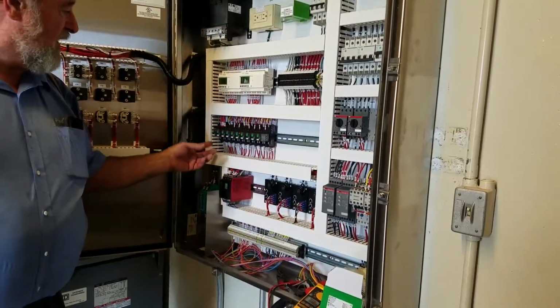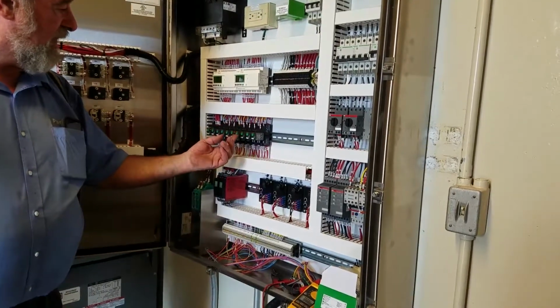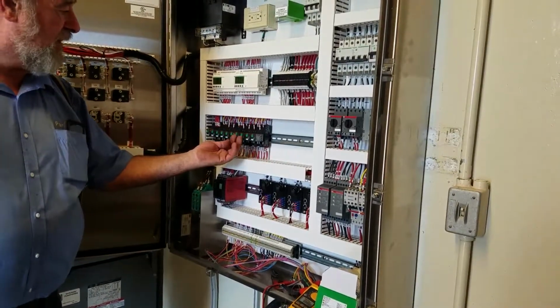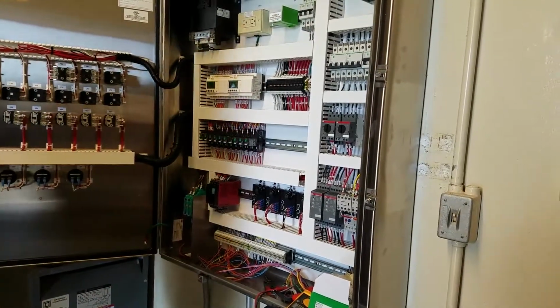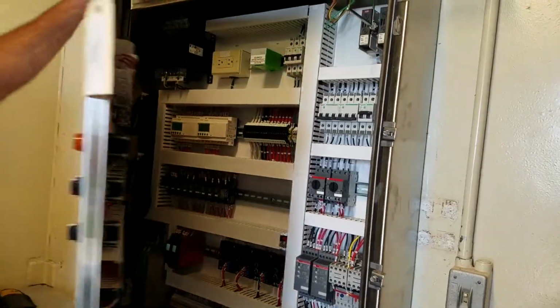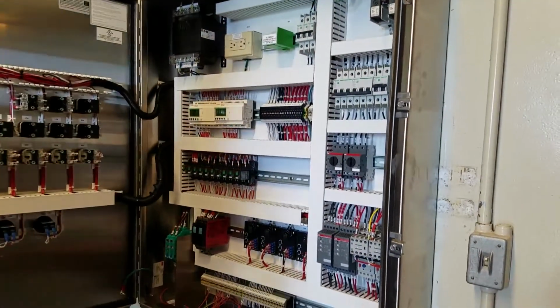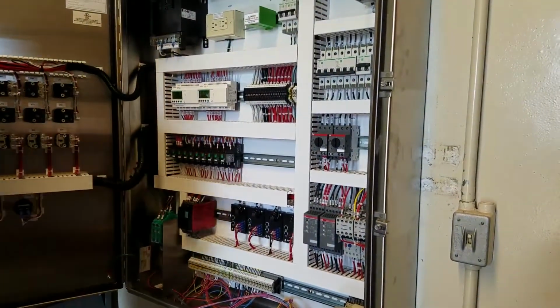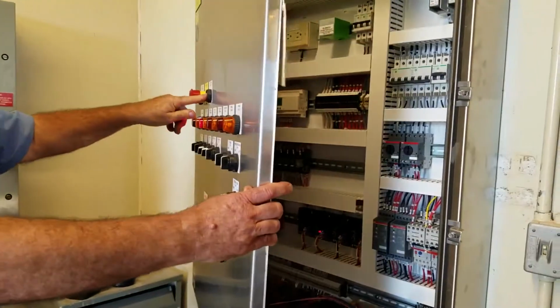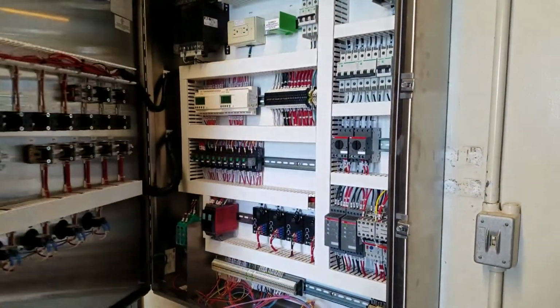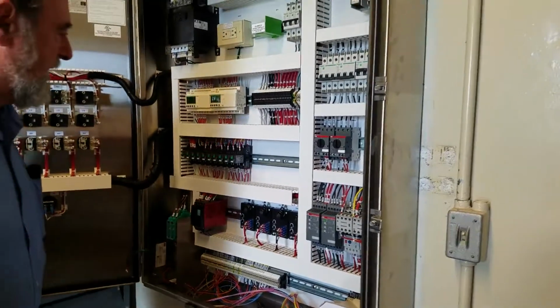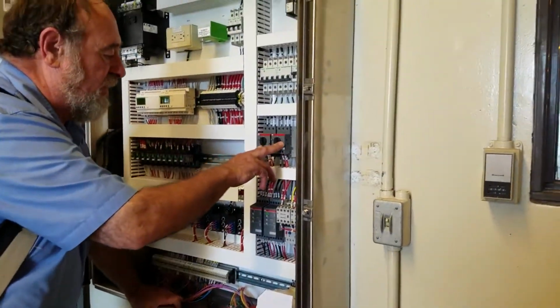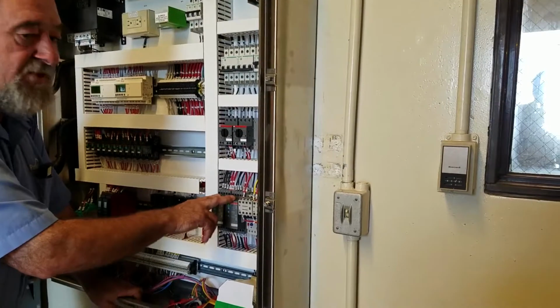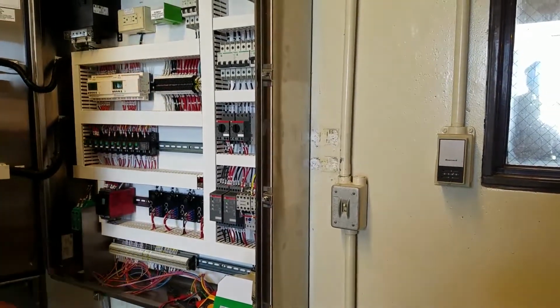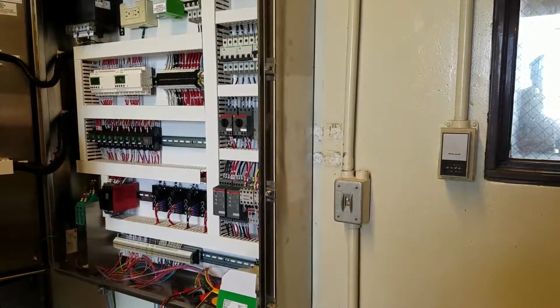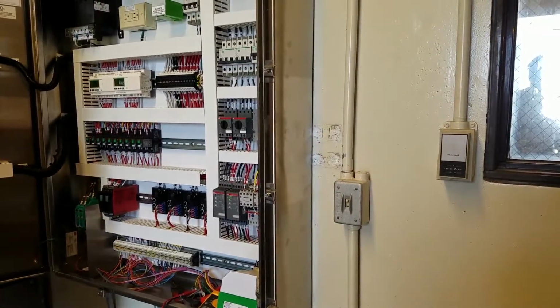These are your control relays. If you wanted to simulate a fault, you take your fingernail, lift that up. Let's see what fault that activates, and it says screen 2 fault. Want to deactivate it, you push that back down, hit the reset button, then it goes back. This is for your soft starts that go to the screens. They use soft starts because they have a lot of torque requirement to get going, and they don't want them to start and stop with a big jerk.